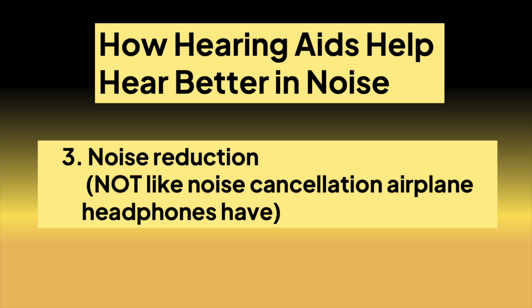The third thing that hearing aids can do to help us hear better in noise is they may employ noise reduction algorithms. However, most of these noise reduction algorithms reduce what we call steady-state sounds — that's fans, air conditioners, sometimes even the internal hissing noise of the circuit of the hearing device. There are some newer hearing aids coming out that have machine learning-based noise reduction, and those are able to almost completely eliminate sounds like a fork hitting a plate — impact sounds. So the noise reduction technology is getting better and better, but right now they don't help tremendously with crowds when the noise is actually the sound of other humans talking.